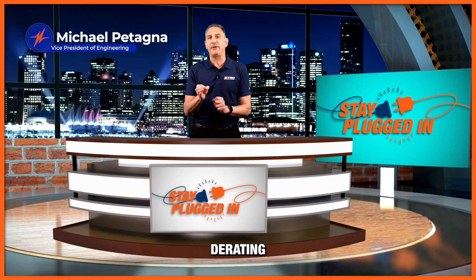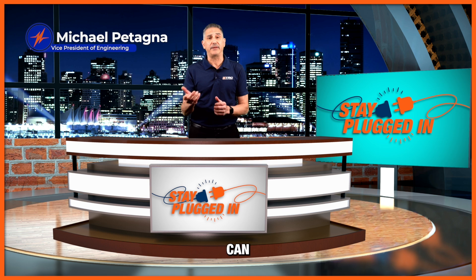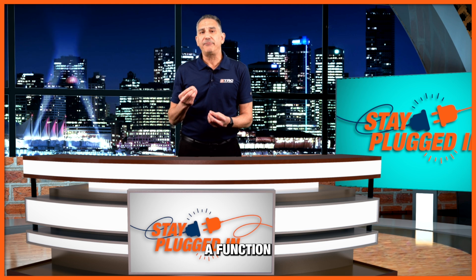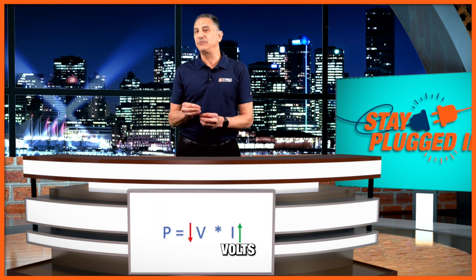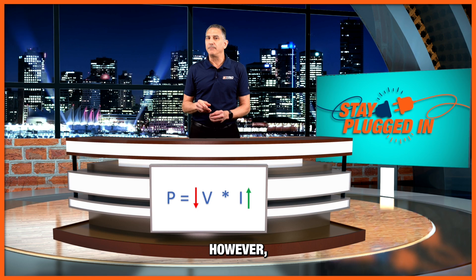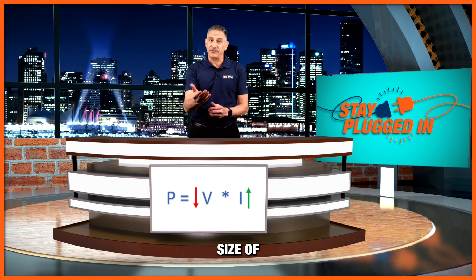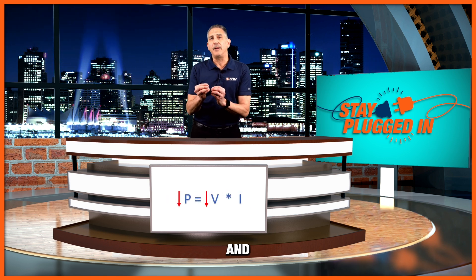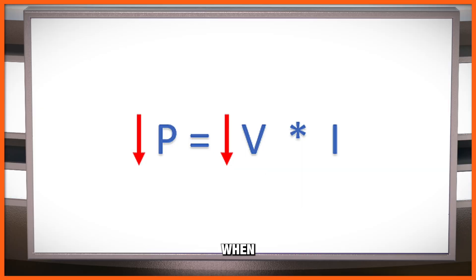The reason why input derating is necessary is a function of the classic power equation: power equals volts times amps. When your input voltage goes down, the input current would go up to keep the power the same. However, the current is going to be limited by the size of the wires and the traces on the input part of that power supply. So to keep the same current and prevent those wires and traces from overheating, when the input voltage is lowered, the maximum power rating is reduced as a function of that lower input voltage.